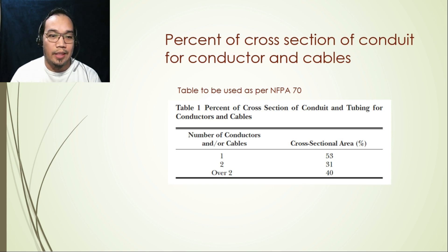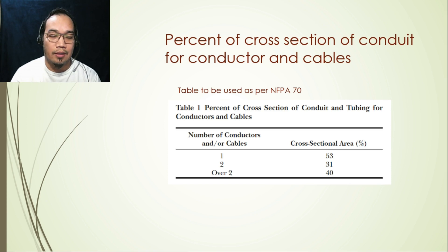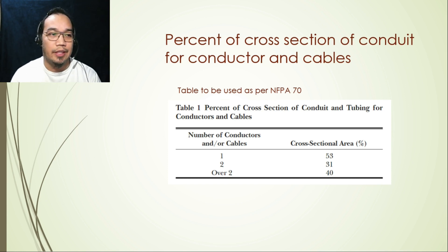If you have two cables, the cross-sectional area of the conduit that can be filled is only 31 percent. For more than two cables, the permitted cross-sectional area is reduced to 40 percent. We will explain this further with examples so you can understand.